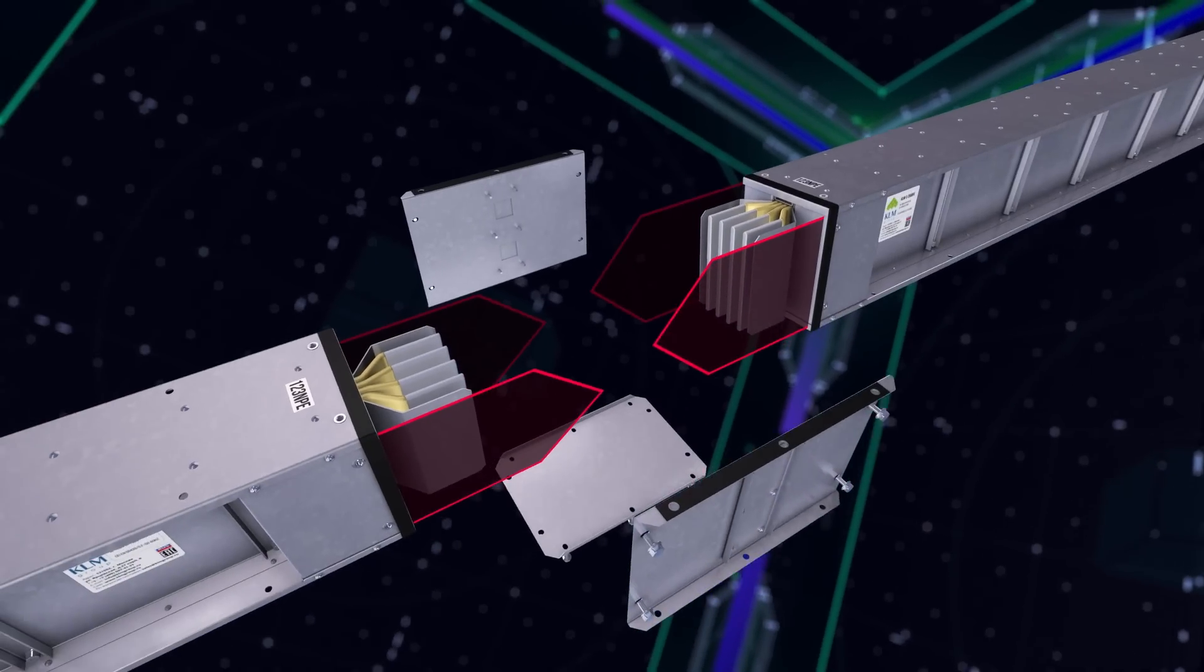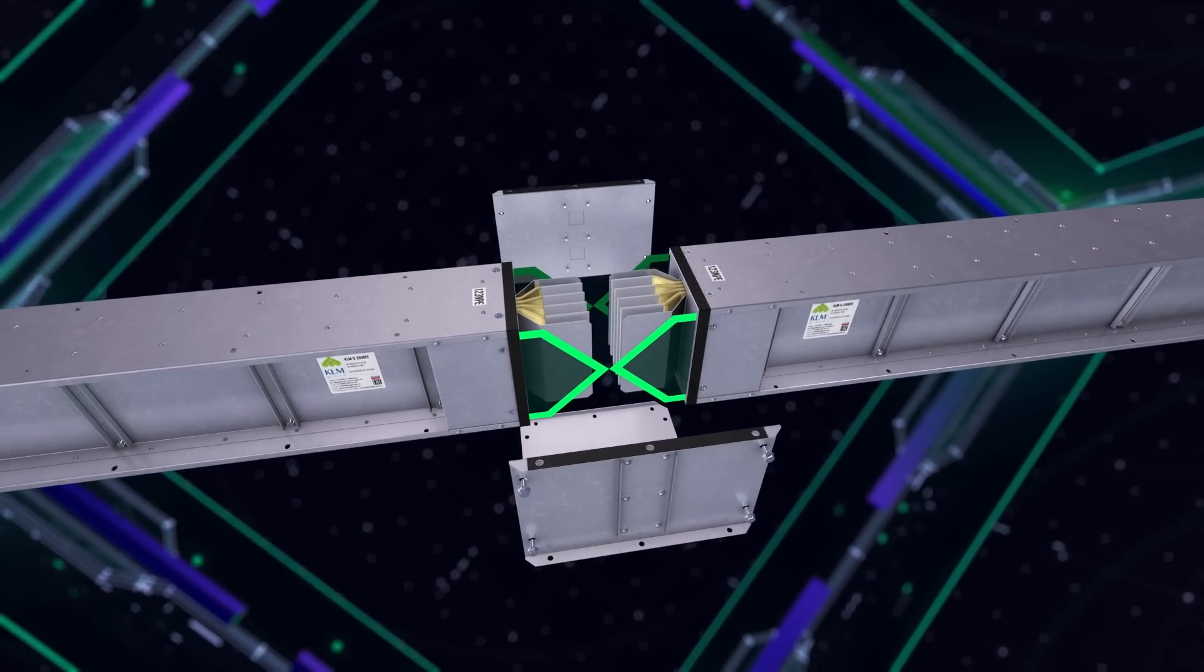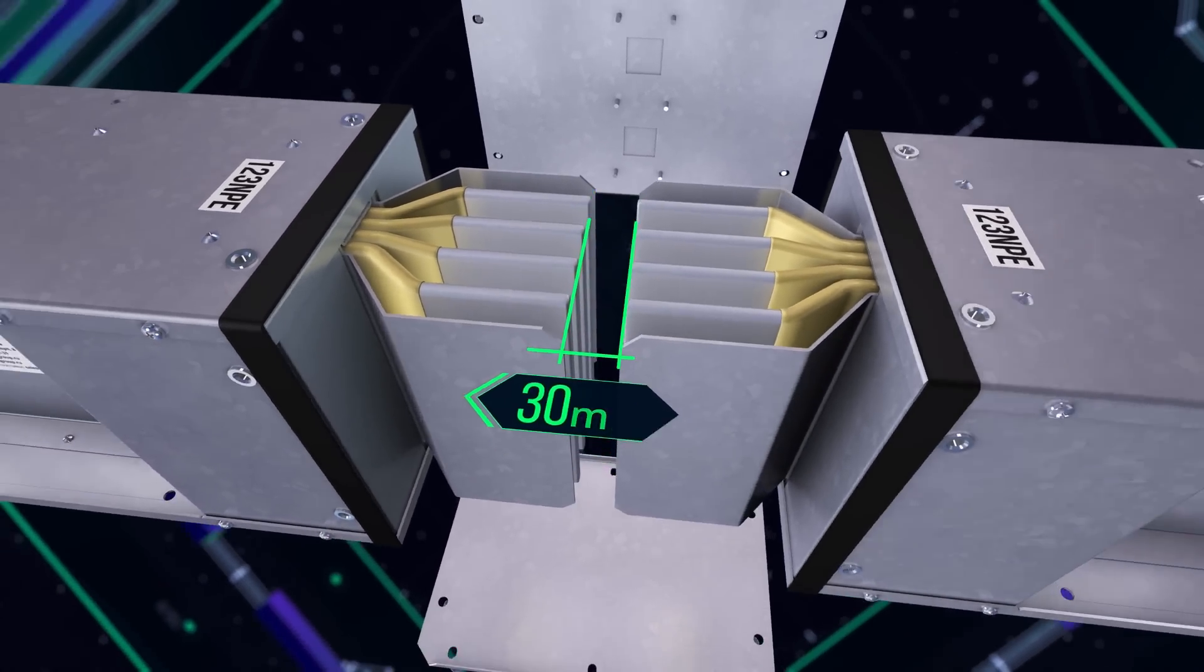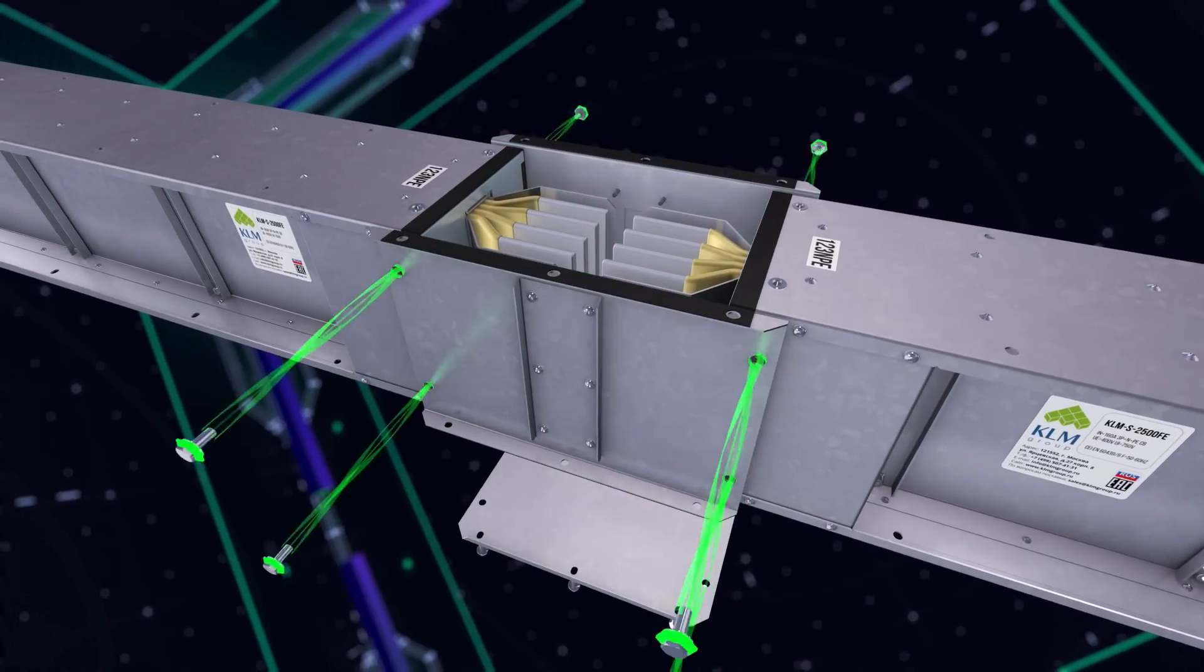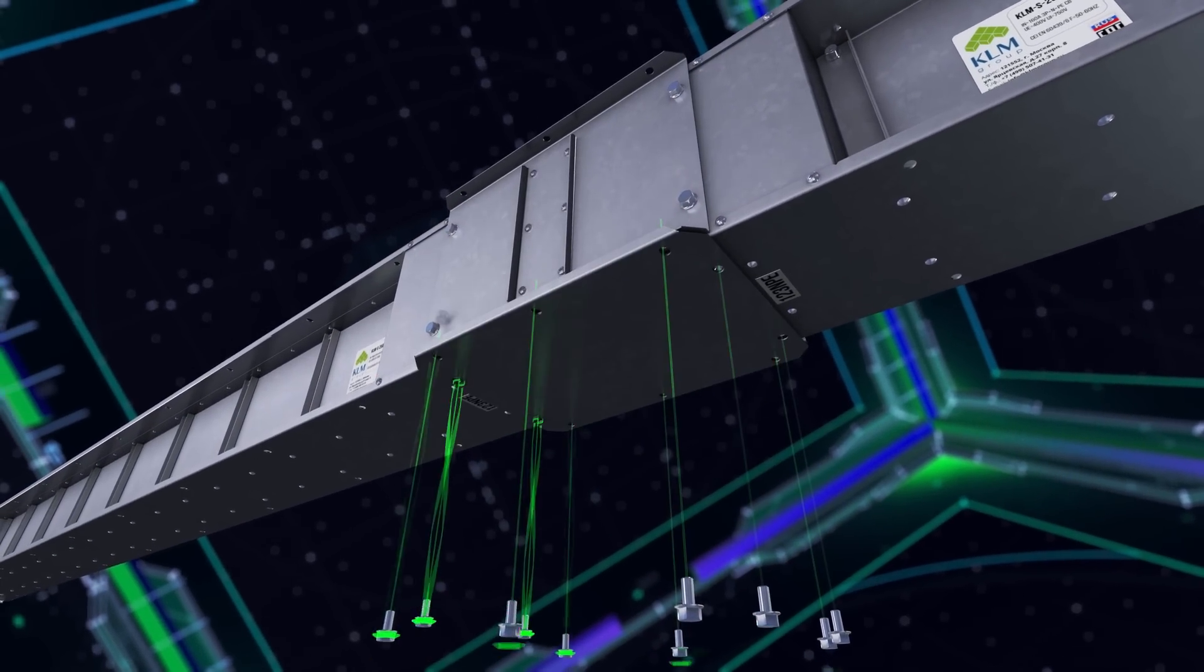When installing sections of the bus bar trunking system, make sure that the junction units are aligned. Position the ends of the current conducting buses 30 millimeters apart from each other. Attach the two side covers and one bottom cover of the junction unit using the bolted connections.